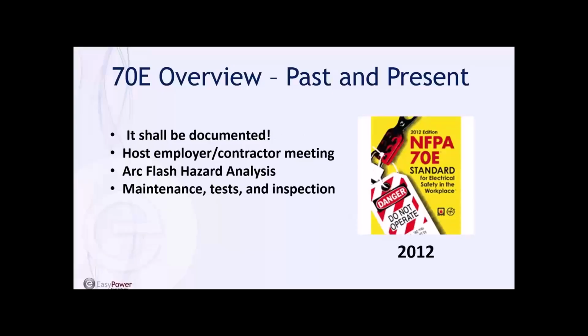Looking at the 2012 edition of the 70E standard, the core theme I'd apply is simply: it shall be documented. Many of the new elements or points of emphasis in 2012 were things that in 2009 might have been additional initiatives, but now required to be documented. Key elements included host employer and contractor responsibility meetings, and the arc flash hazard analysis itself needed to be documented. Interesting enough, in 2009 there was no need to write a study report — that only came about in 2012. Maintenance, test, and inspection of equipment was also brought forth in the 2012 standard.